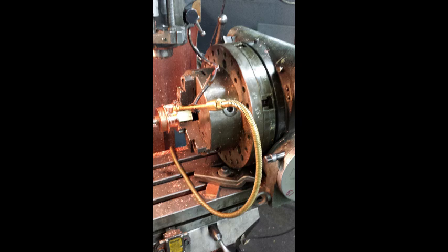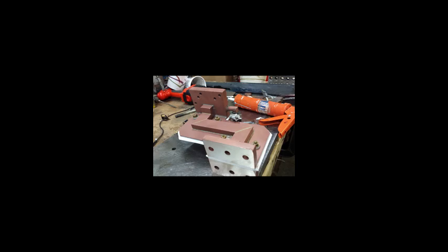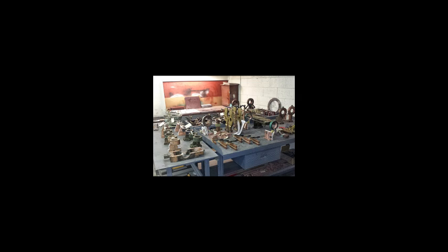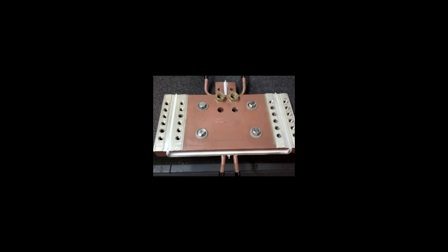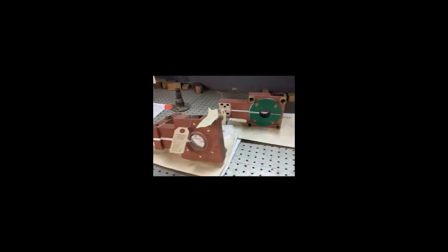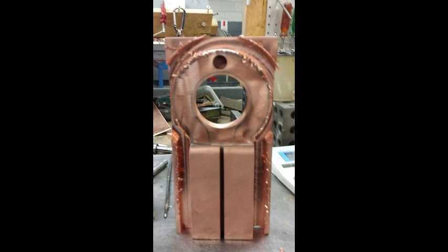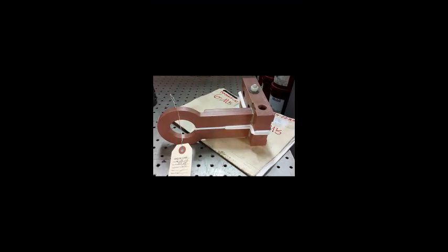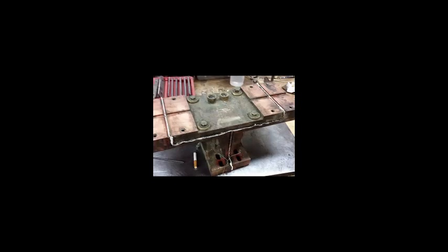Induction heating can be used in different industrial applications by providing a highly efficient and controlled way to heat metals and non-metal parts. When considering heating methods, the most basic and widely known is open flame heating. In this process, a flame heats the part and filler metal is added to the joint, but less than half of the heat is absorbed by the metal, while the rest is wasted in the environment. To compensate, multiple flames are sometimes used, but this method lacks precision and repeatability, making it unsuitable for high-volume manufacturing.